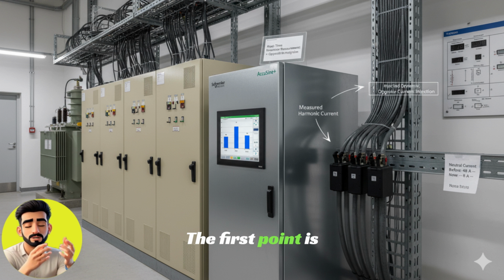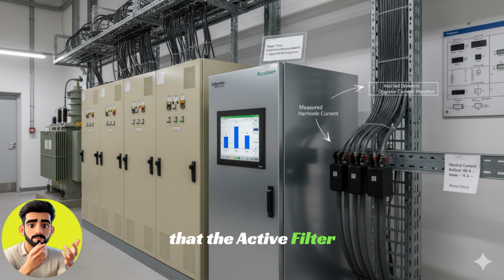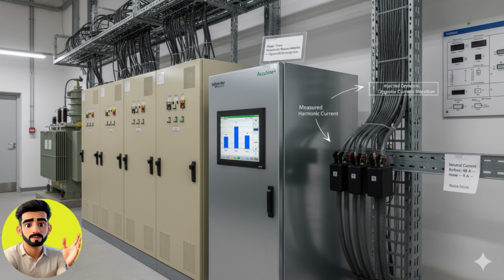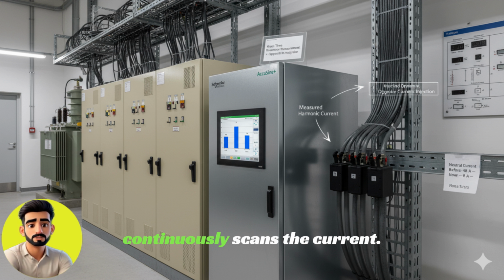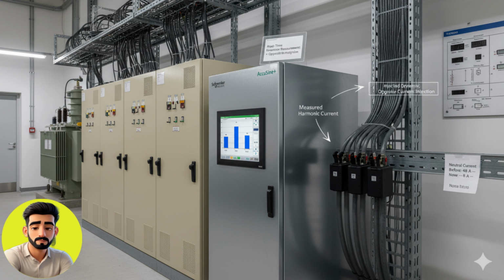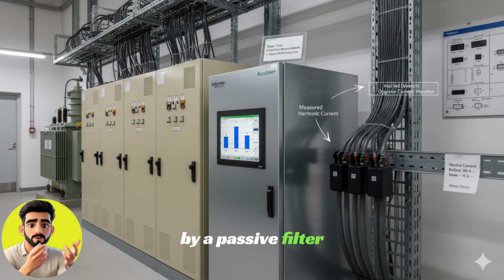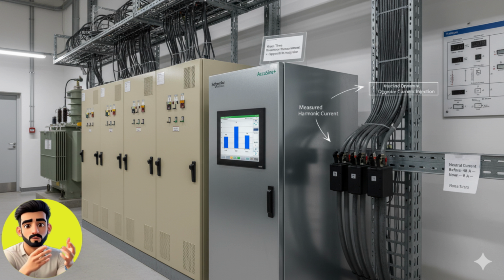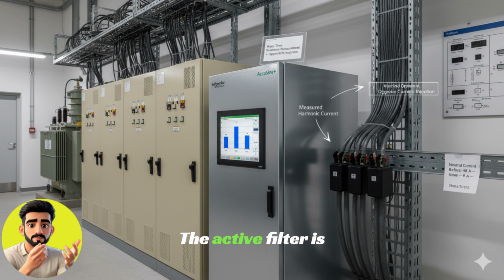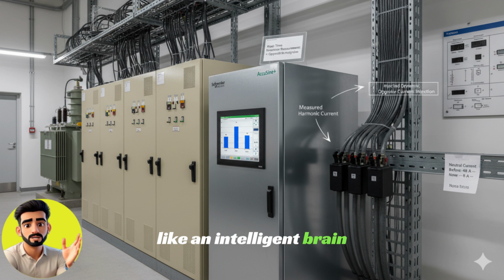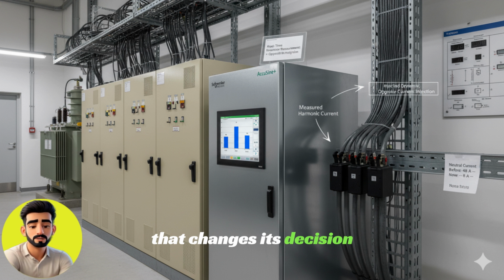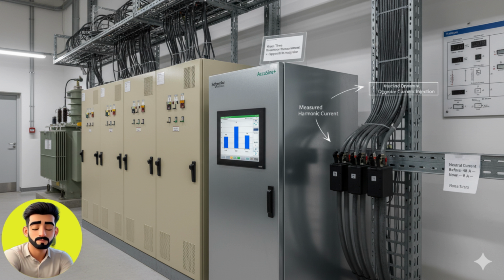The first point is that the active filter measures harmonics in real time. The active filter system continuously scans the current. The harmonic with a high value is immediately identified by the filter. This cannot be done by a passive filter because a passive filter only targets a fixed harmonic. The active filter is like an intelligent brain that changes its decision every second in the system.